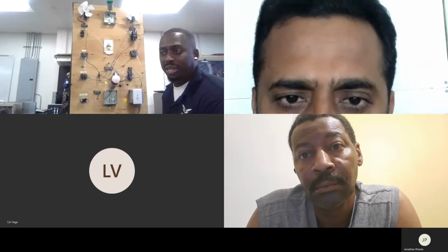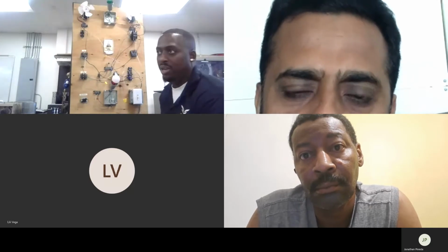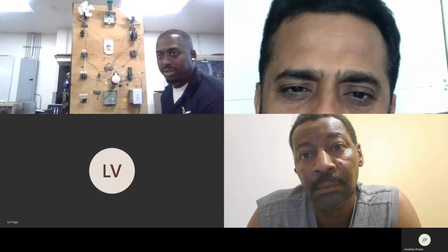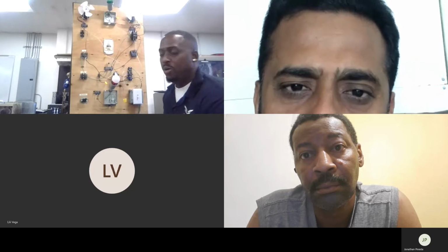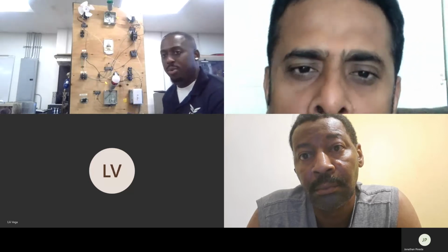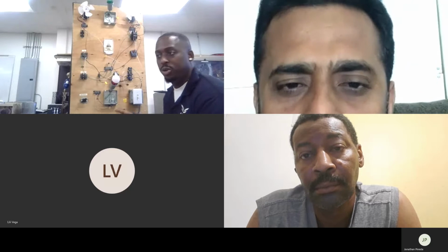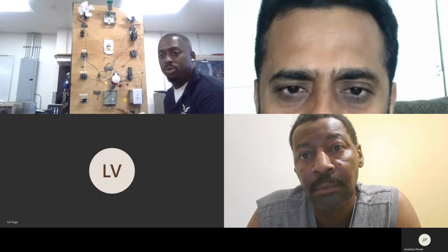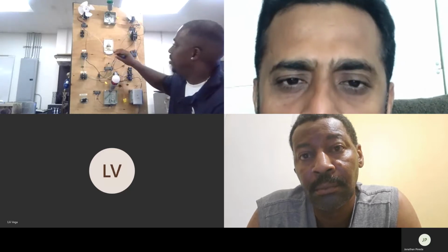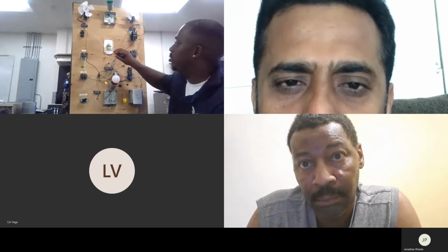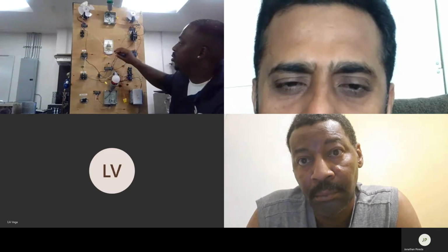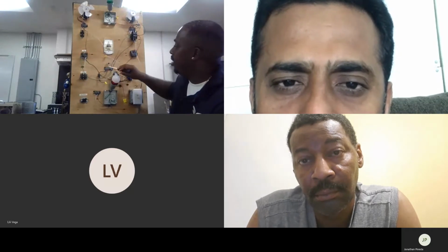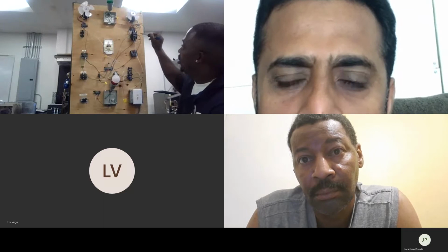But it's not always the case. You might pull the thermostat off and have a bunch of red and white wires, and then you're like, well what's going on? Which is why you don't want to get hung up on the color code. You want to make sure you know what each terminal is for. If you know, I don't care if it was pink — if you know Y is for cooling, then you know this pink wire needs to be connected to our contactor coil, because this is for our cooling.